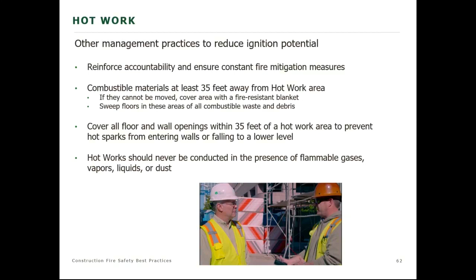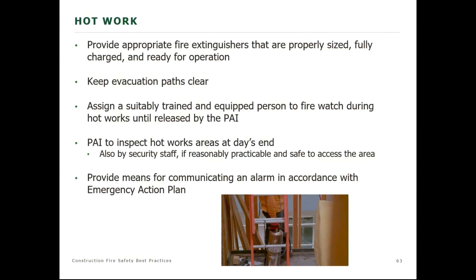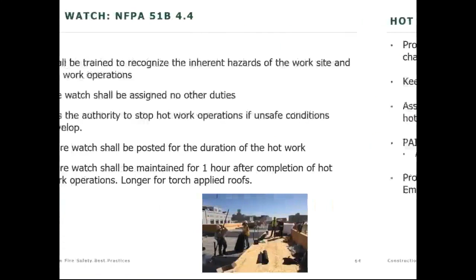After the hot work is completed, they also go back and make sure that the fire watch is in place, and they keep all the paths clear and reasonably clean. Now, the fire watch for hot work, not to be confused with the guard service fire watch, the person can have no other duties.